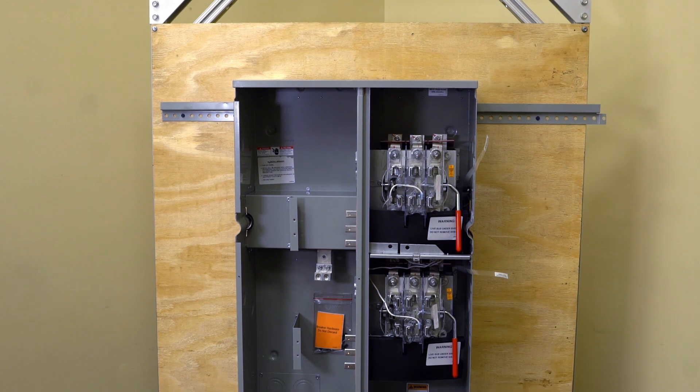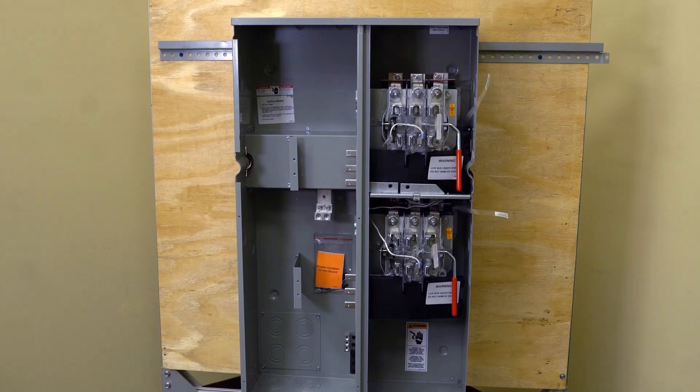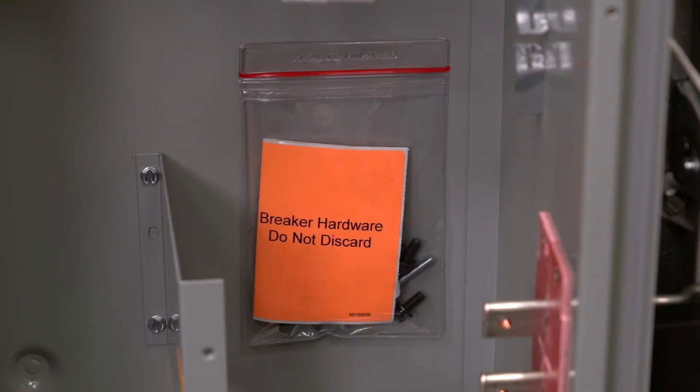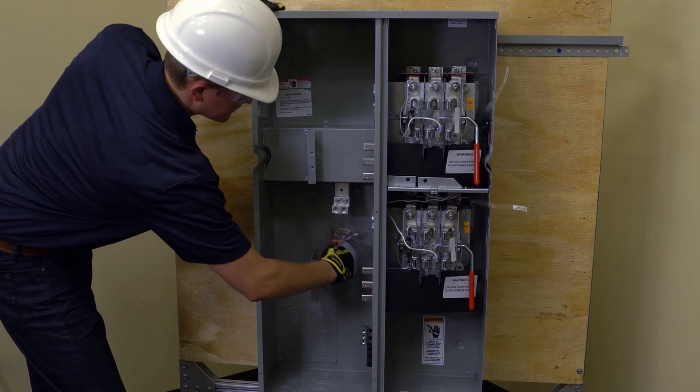When installing three phase in, three phase out stacks, one of the most important things to be aware of is that all of the mounting hardware for the breaker is located in the components bag along the back wall of the unit. It is crucial not to throw this bag away until you are certain the contents are not needed. Be sure to remove the components bag from the enclosure prior to energizing.